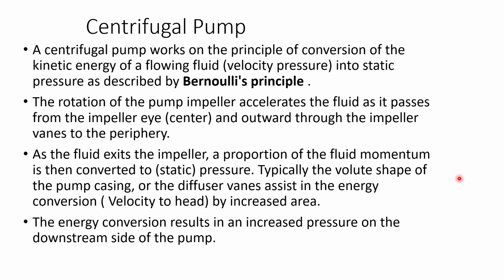Typically, the volute shape of the pump casing or the diffuser vane assists in energy conversion and converts velocity into head by increasing the area. The energy conversion results in an increased pressure on the downstream side of the pump.